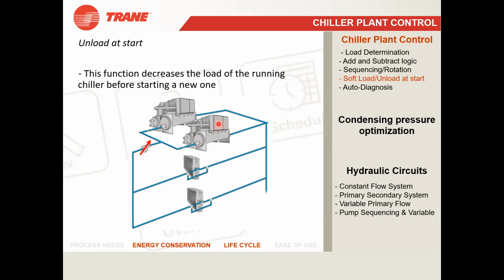So one chiller is running, and it has understood that it has to add one more chiller. So what will it do? The first chiller will reduce its capacity to the minimum percentage of load, maybe 15% or 20% as per the chiller manufacturer configuration. So it will reduce itself to that percentage of load, and then it will start another chiller. And after that, both chillers will be loaded gradually.